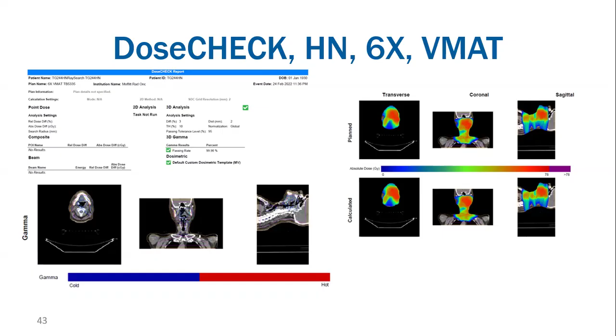So these are just some results. For each plan, as you can see, 0.3% off, 1.2% off, negative 0.1% off, 0.9% off. So each time we got within that 3% tolerance that we tried to achieve. We then had Sun Nuclear software that allowed for a second check. We performed this sort of secondary dose calculation, which performs a gamma analysis, and we compared them as well. This is a little bit less important because it's not actually comparing to an actual measurement.